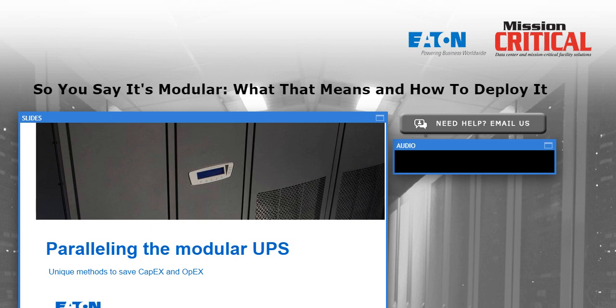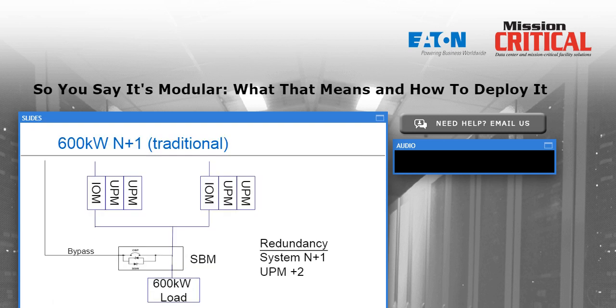What if I want more power than I can get in a single lineup of one of these modular UPSs? Most of us vendors top out for a single UPS, even if it's a modular design, at around 1,000, 1,250, or 1,500 kilowatts. That'd be 1.5 megawatts of power. Well, we have a lot of clients who need even more power than that. Some of them are looking for 3 and 4 and 5 and even 10 megawatts of UPS power. In many cases, we can split that up into discrete systems. But how big can I get with a single UPS, and does it give me an advantage to have a modular design? Well, let's take a look at some very basic block diagrams here.